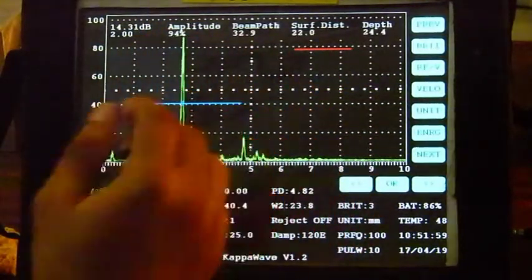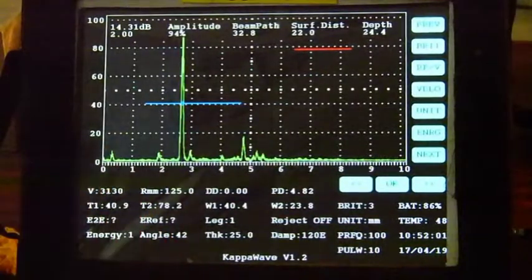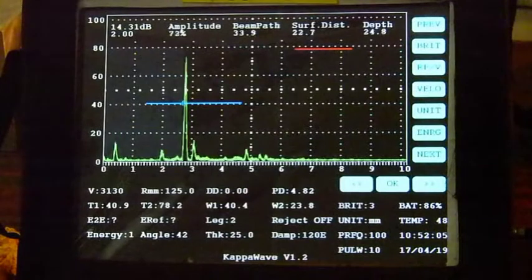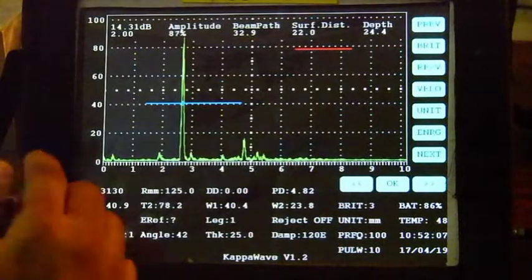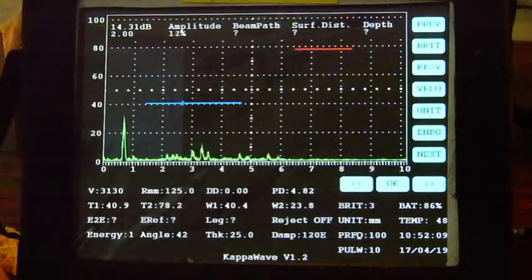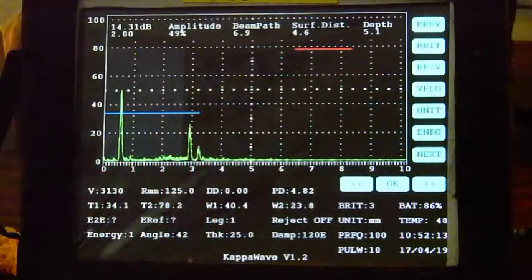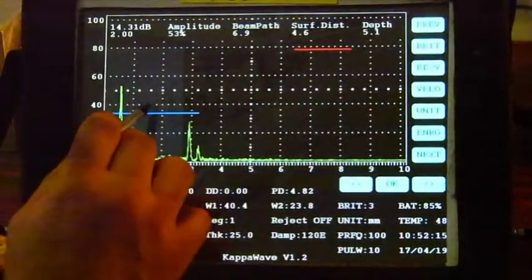So as a signal is gated, the instrument is geared to give you the beam path, surface distance and depth. In this case the depth is shown as somewhere about 24 mm. Another signal when you gate it says it is about 5.1 mm in depth.